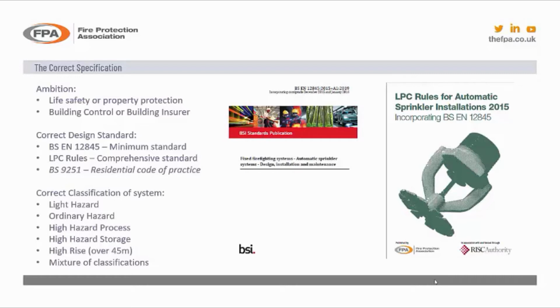It's a minimum standard. And on the right hand side, we also have the LPC rules, which is more comprehensive. It builds on the base document of the BS EN 12845, and it adds on additional requirements that have been written by insurance experts and industry to enhance the sprinkler system to provide elements of property protection. So it's an overall standard that covers both the property and also life safety.